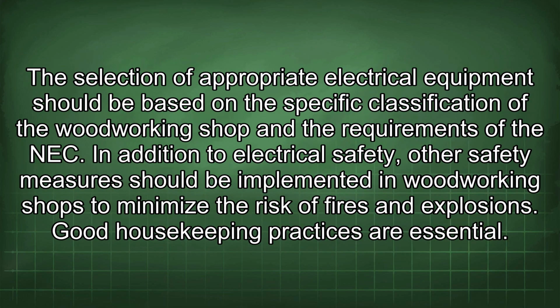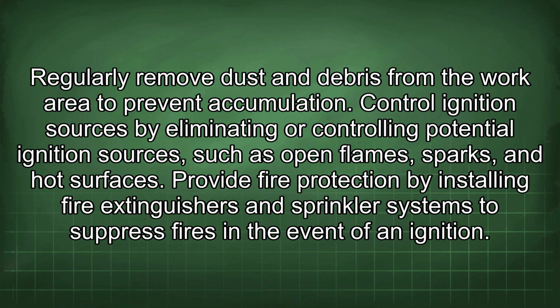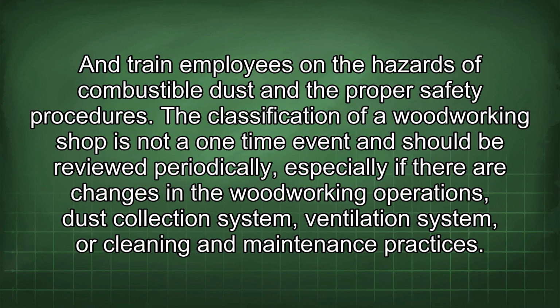A selection of appropriate electrical equipment should be based on the specific classification of the woodworking shop and the requirements of the NEC. In addition to electrical safety, other safety measures should be implemented in woodworking shops to minimize the risk of fires and explosions. Good housekeeping practices are essential. Regularly remove dust and debris from the work area to prevent accumulation. Control ignition sources by eliminating or controlling potential ignition sources, such as open flames, sparks, and hot surfaces. Provide fire protection by installing fire extinguishers and sprinkler systems to suppress fires in the event of an ignition. And train employees on the hazards of combustible dust and the proper safety procedures.